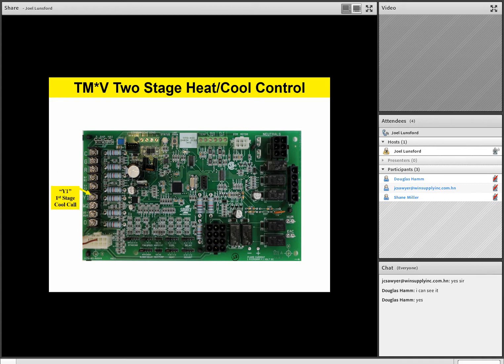Now again, team, we always recommend that you have a two-stage thermostat on a two-stage product, but if you're stuck with a single stage heating situation, we can still give you some staging, which we'll talk about in a little bit. Now this board has a unique feature. It's called dehume. That dehume is actually a cooling dehumidification function. And you'll notice a little bit later on, when we start talking about some different jumper functions down in the lower part of the board, there's a jumper down there that says humestat.